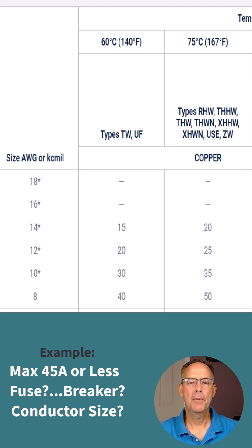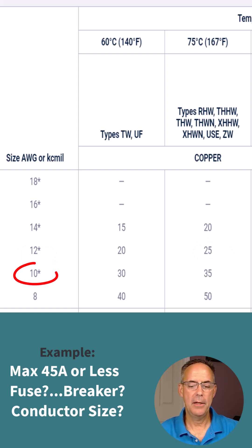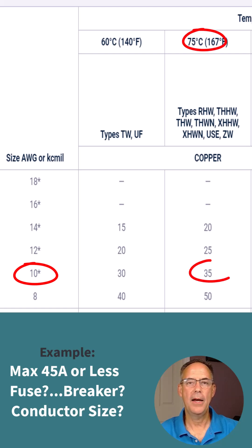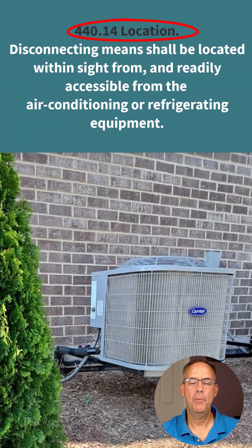Based on Table 310.16, a number 12 conductor would only be able to handle 25 amps, so we would have to go with a number 10. A number 10 in the 75°C column would be 35 amps, so that would be plenty for this installation.